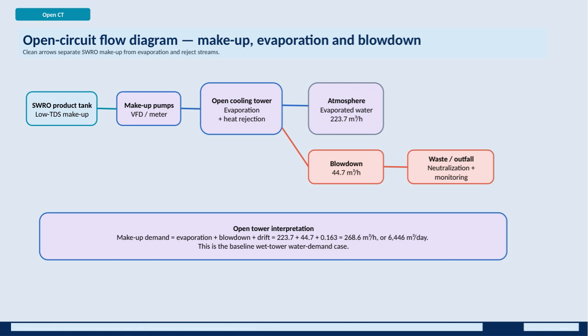This water is then pumped by the makeup pumps, which are equipped with variable frequency drives and meters to carefully control flow rates. The open cooling tower is where heat rejection takes place through evaporation, releasing water vapor into the atmosphere. In this process, about 223.7 cubic meters per hour of water is evaporated. Additionally, blowdown of 44.7 cubic meters per hour occurs to prevent salt buildup, and this reject stream undergoes neutralization and monitoring before disposal as waste or outfall.